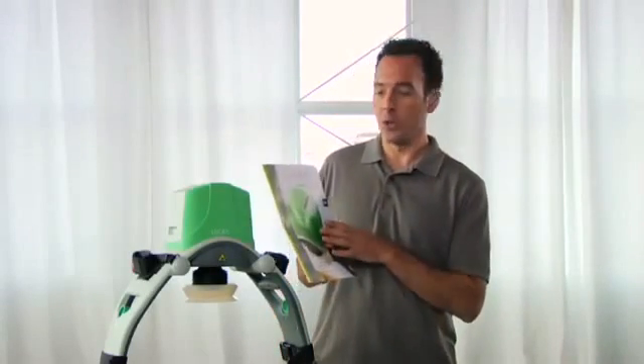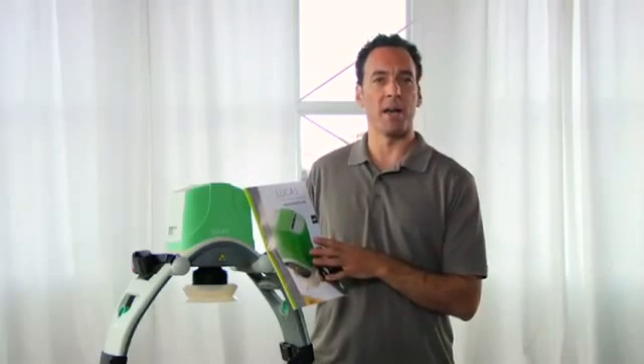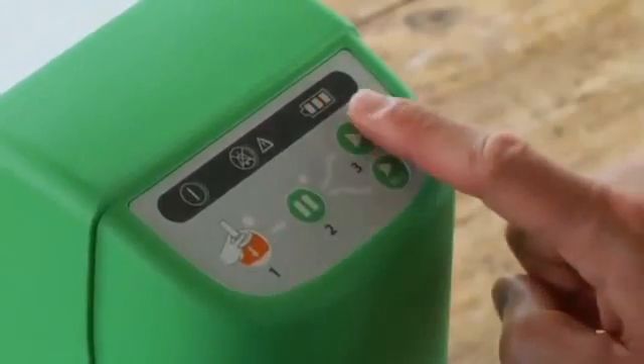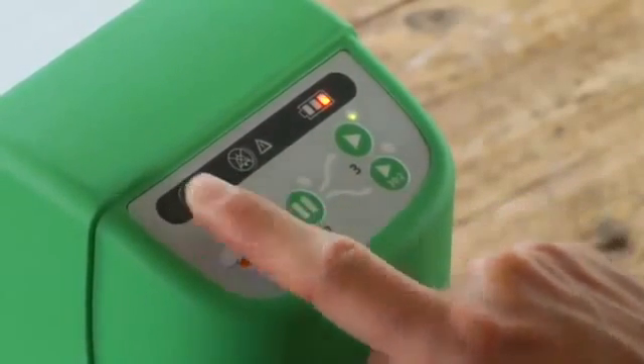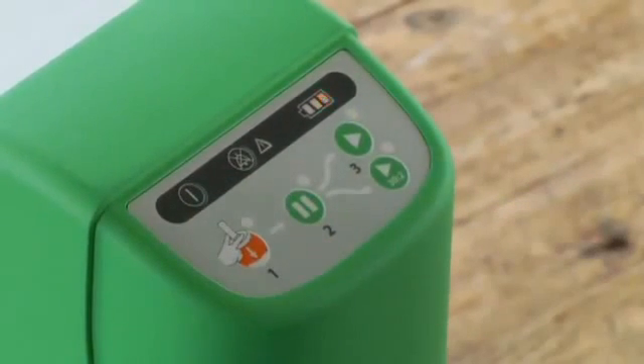You should learn the various warning and battery status indications — they're all in the instructions for use. Keep it handy in the bag. What you're watching for is a red or orange LED, together with an alarm signal. That means you have a low, empty, or defective battery.